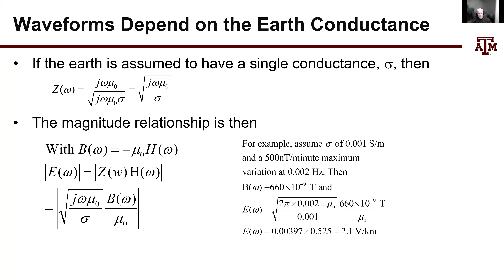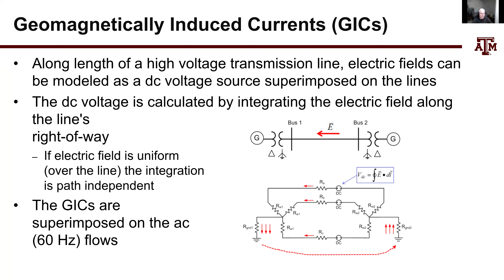When you have an electric field over the high voltage transmission system, it produces geomagnetically induced currents, GICs. These are produced whether you have a geomagnetic disturbance or E3 coming off of a HEMP event. To get the voltage, you integrate the electric field along the line. If the electric field is directed along the line, it's a straightforward integration; otherwise we usually do piecewise linear integration to get an assumed voltage - a quasi-DC voltage, since its frequency is much less than 1 hertz, well below the electric grid frequency.